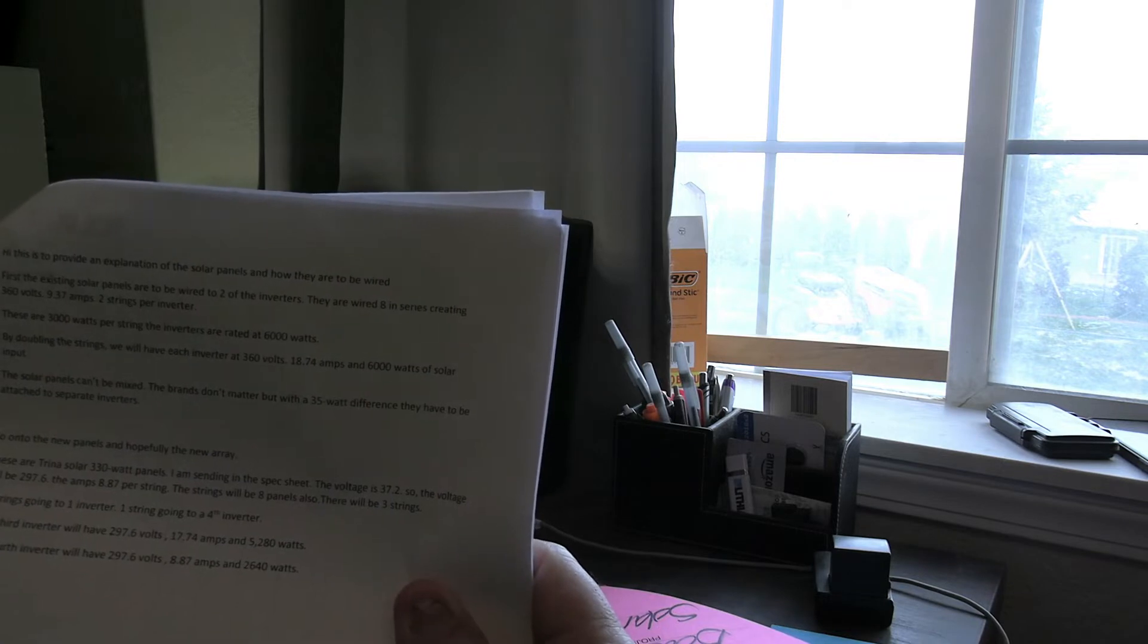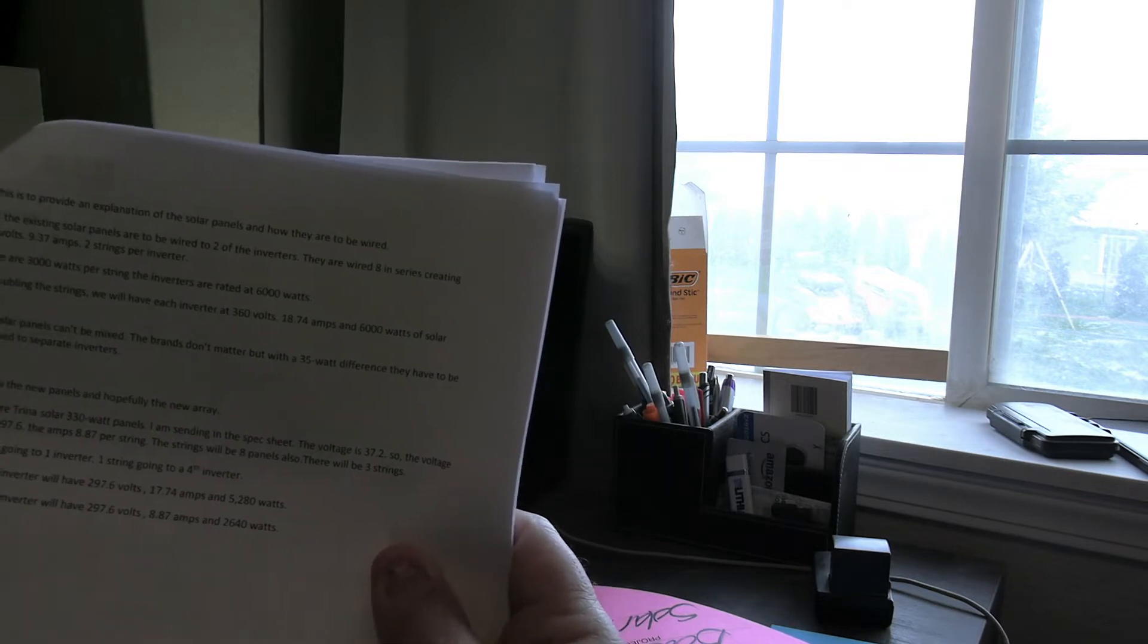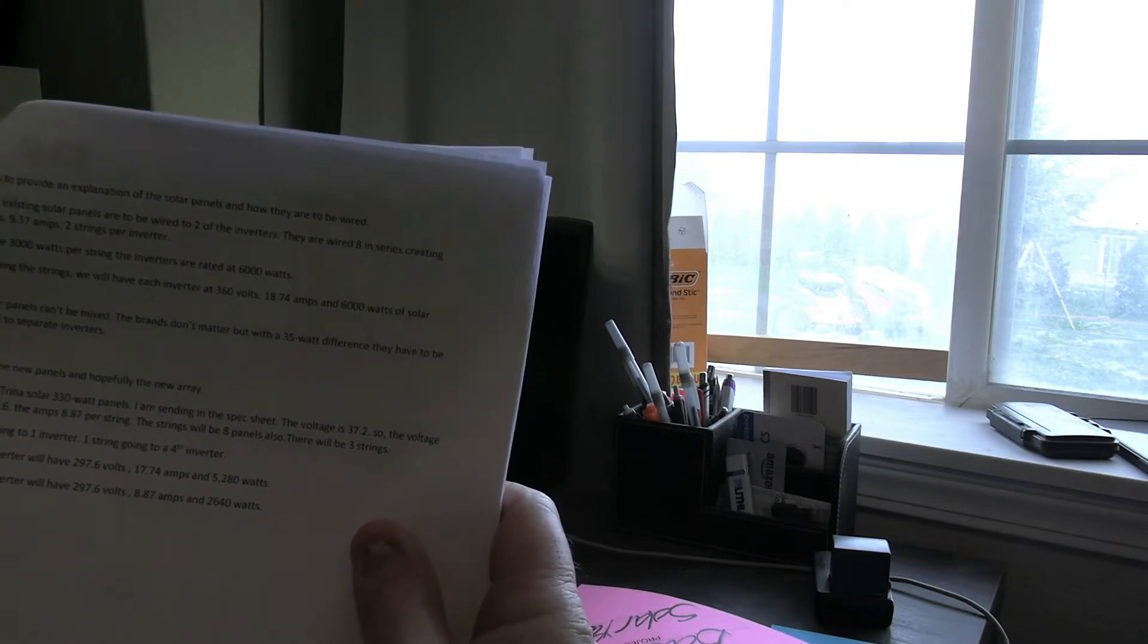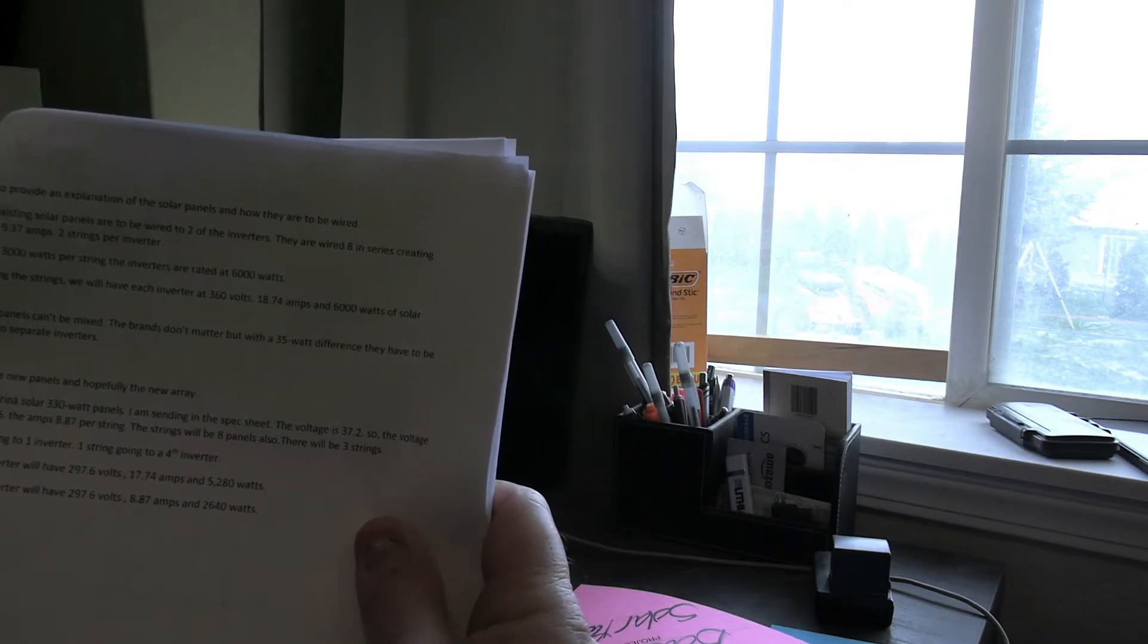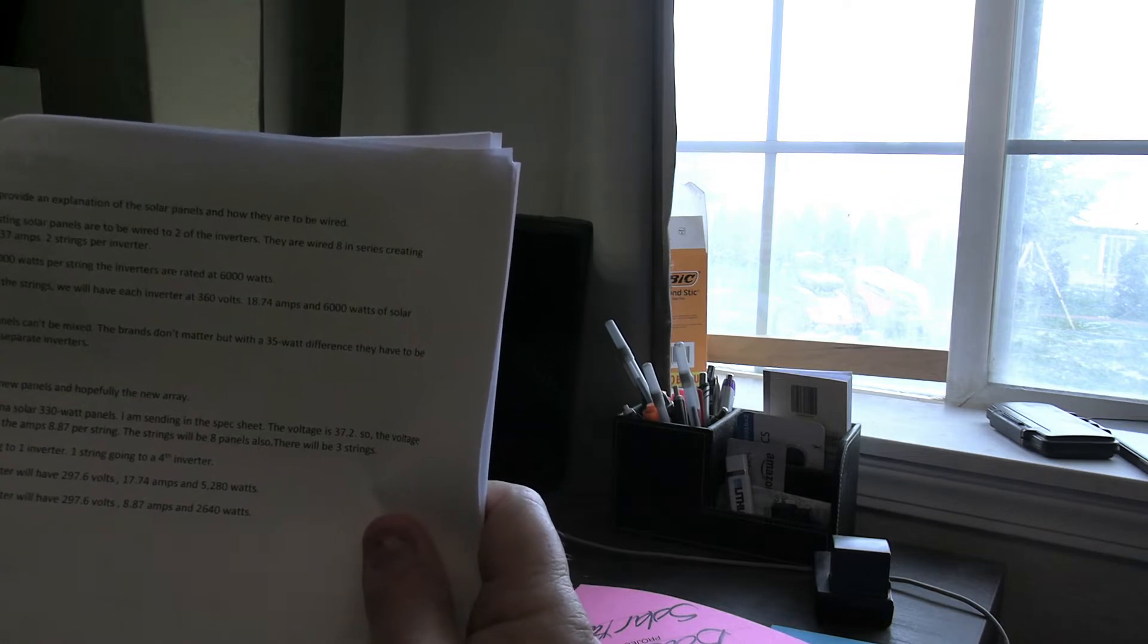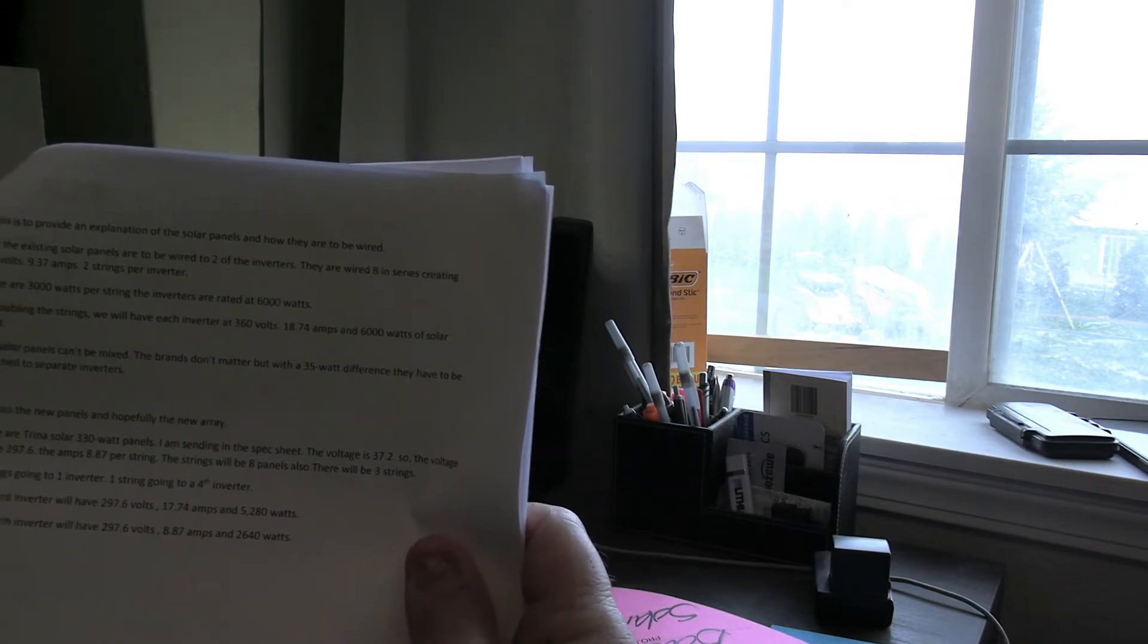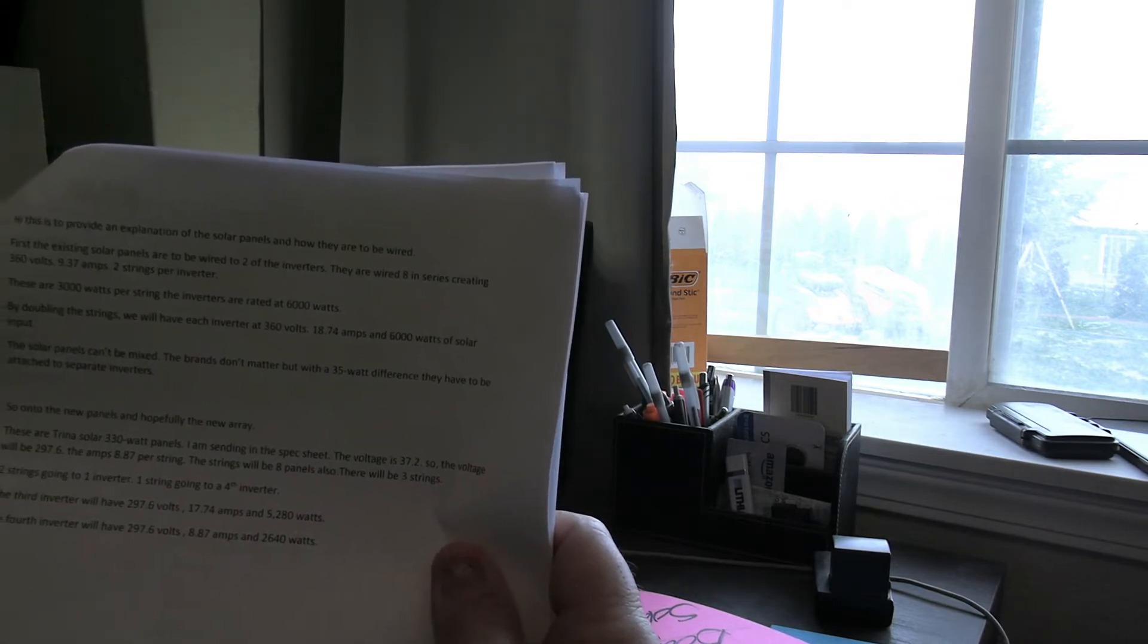These are 3,000 watts per string. The inverters are rated at 6,000 watts. By doubling the strings we will have each inverter at 360 volts, 18.74 amps and 6,000 watts of solar input.